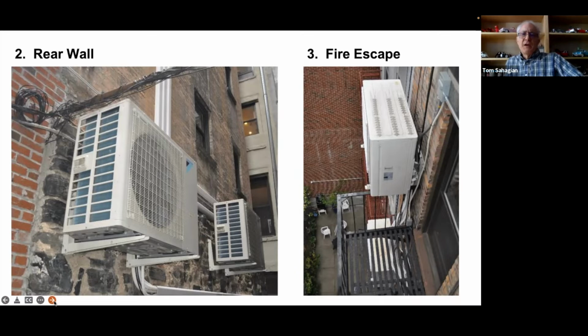We did this because we wanted to minimize the length of the refrigerant runs, and also because we wanted to show that you don't have to put all of these outdoor units on the roof. There are many reasons why you wouldn't want to do that: it takes up a lot of space, and if you have to replace the roof in the future, it makes it more difficult. Especially as the building gets taller, the refrigerant runs get longer, to the point where you get past the recommended length specified by the manufacturer. So we found 3 different locations, and so far they've all worked really well.